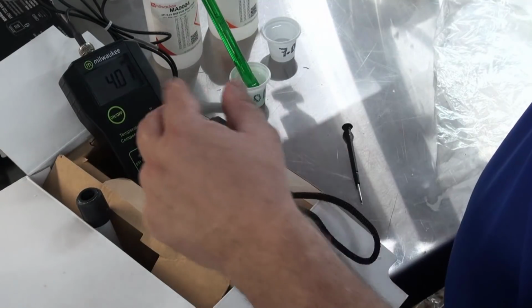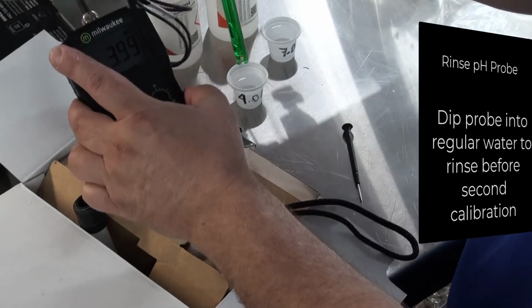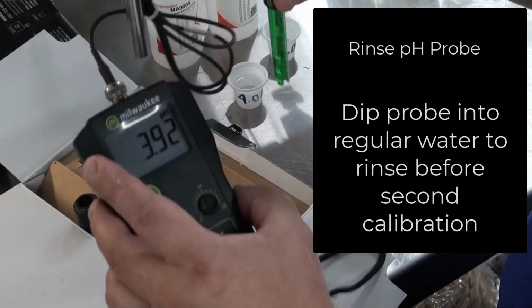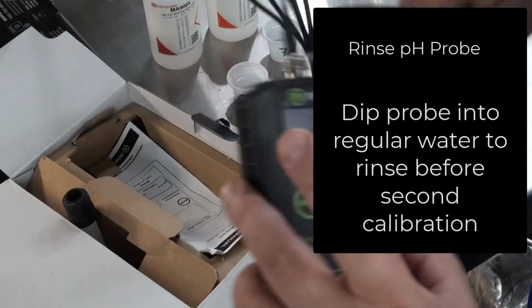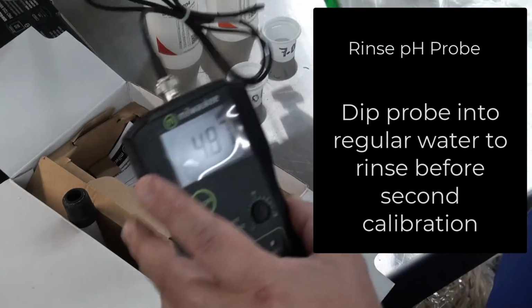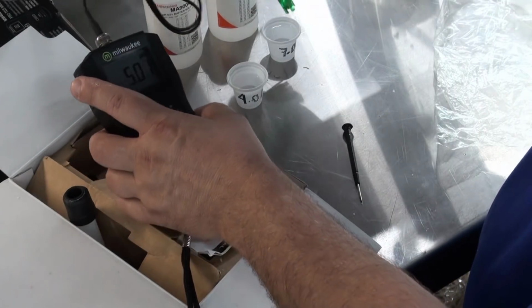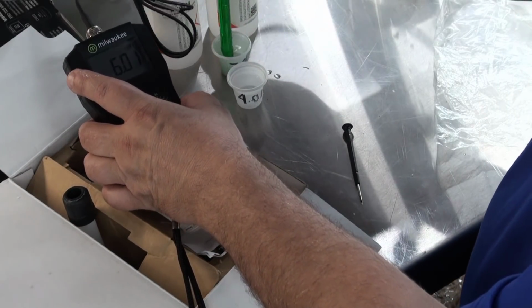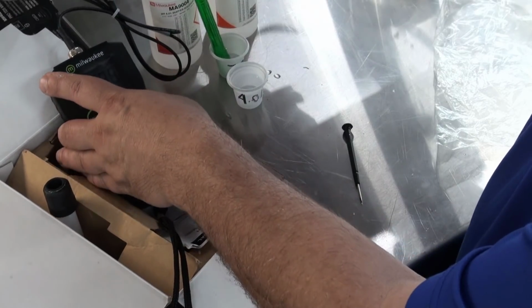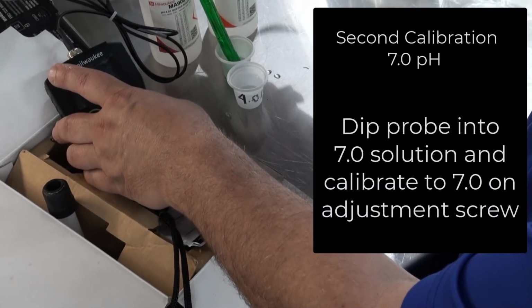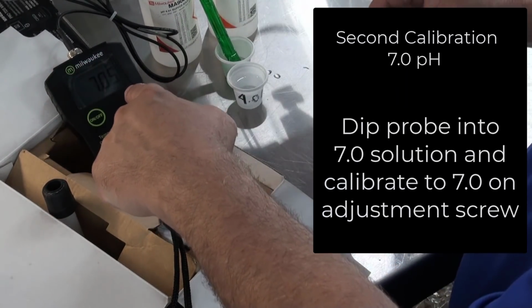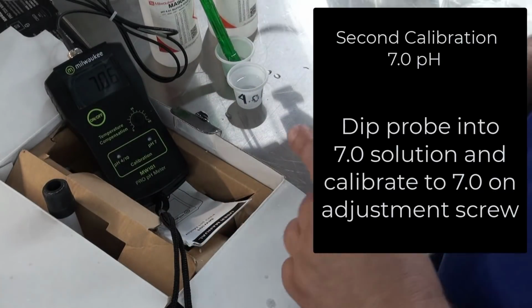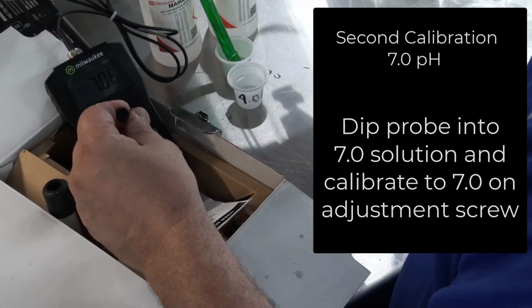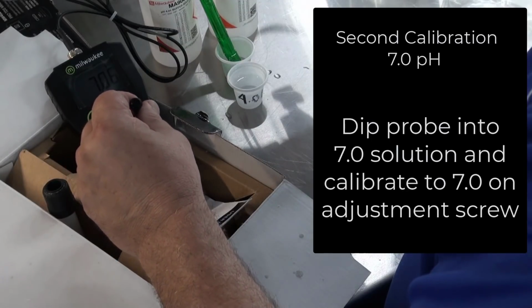Then once again, so I don't contaminate the 4 solution with the 7, I'm going to rinse it one more time in regular water. Normally I would dry this with a paper towel, but my shirt does just fine. And we're going to stick it in the 7.01 solution. Okay? And you'll notice that the meter is already reading. Now, on this particular one, I went a little higher. Normally when they come in, they're dead on. But we can adjust it.